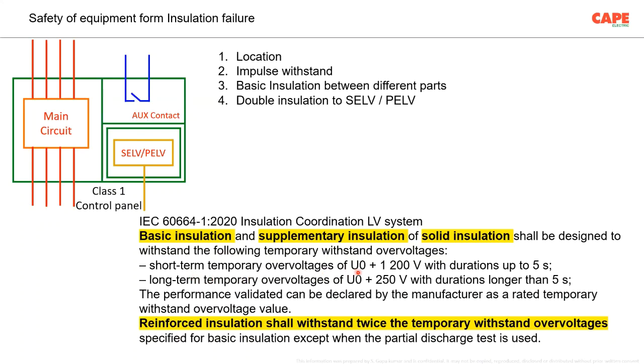Short-term temporary overvoltage: U0 plus 1200 volt with duration up to 5 seconds. Long-term temporary overvoltage: U0 plus 250 volt with duration longer than 5 seconds. As I said, this is between line and earth. The panel board has to be made in such a way that it is able to withstand these voltages.